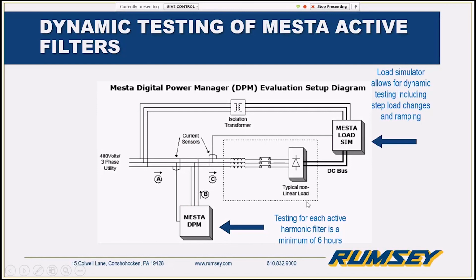But at the same time, to eliminate many of the problems that older active filters had, we have a slow integration control to make sure that we're not only predicting what we think the VFDs are going to do, we're waiting for that to actually transpire on the line.